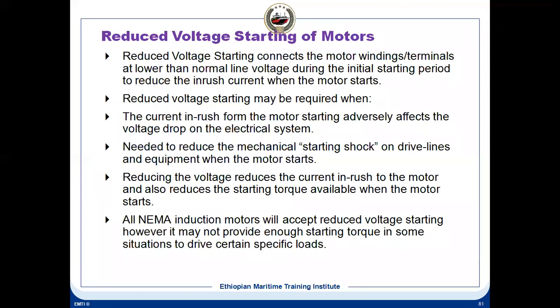It's also needed to reduce the mechanical starting shock, because when you start at full voltage, there will be a shock to the motors. That is why we use direct online starters only for motors below 10 HP, and above 10 HP we use star delta starters, auto transformer starters, or soft starters. You see the difference between a star delta starter and a soft starter. Soft starter means there is no jerk. The voltage is slowly ramped up.